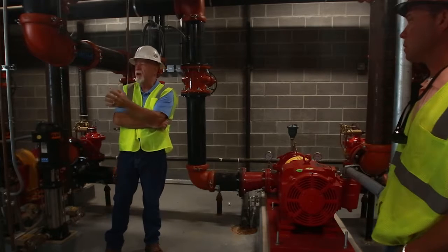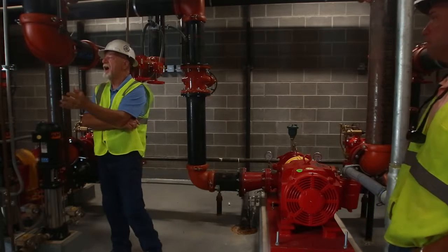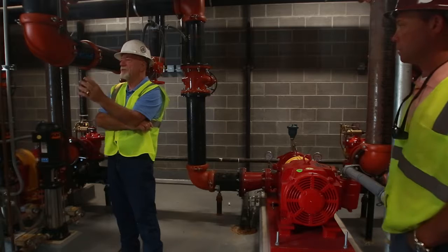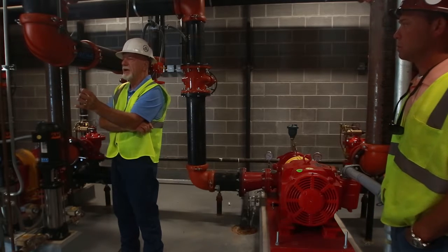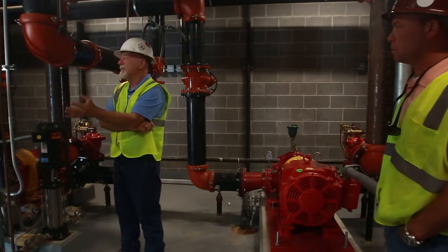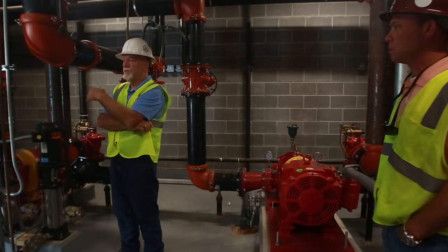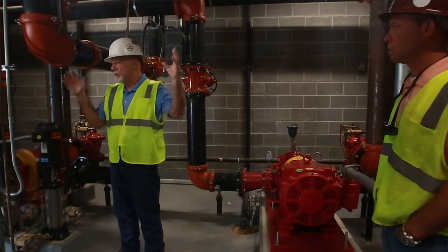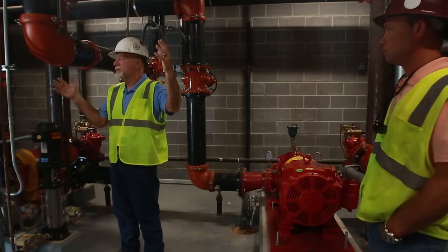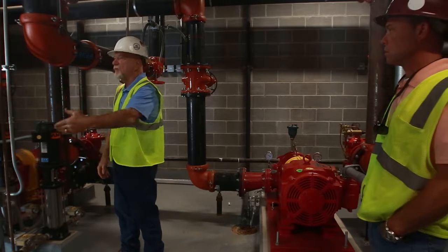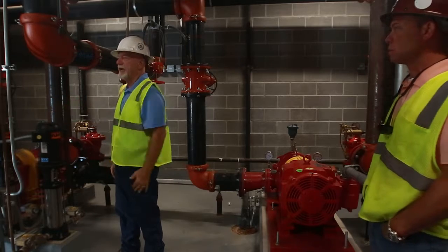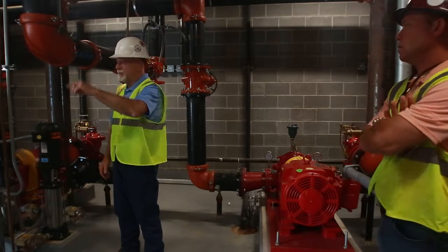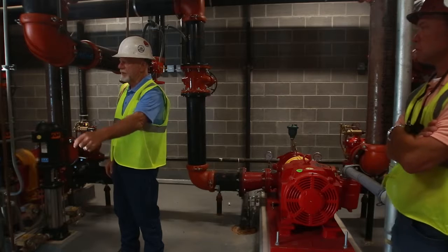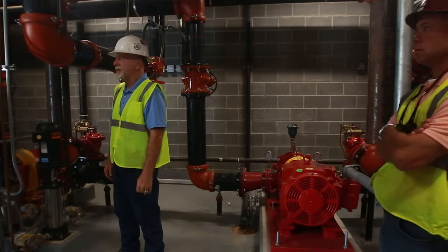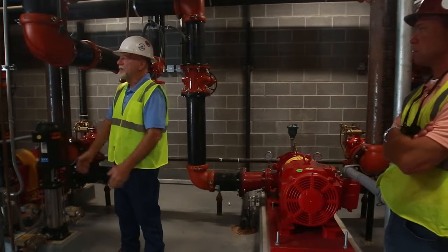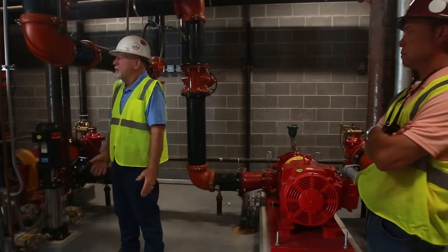Well, quite honestly, if you have a fire, it's not going to wait for that perfect circumstance, whatever it may or may not be. My recommendation is, and always is, you will walk into the room, and if the pressures are normal to a degree, something weird hasn't happened, and you guys know these systems from looking at them day in and day out, hit it like you do on the other systems, open up the pressure relief off the side of the controller, put that thing in action and let it do what it's going to do. Because that's the real work.